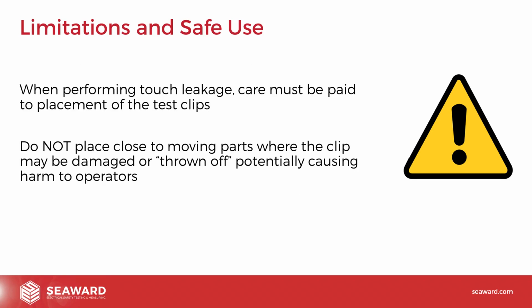When you're performing the touch leakage test, you must pay attention to where you're going to put the clip. Obviously, certain metal parts will move. What we don't want to do is place the clip somewhere that could be damaged, causing damage to your equipment, or thrown off, potentially causing harm to your operators.